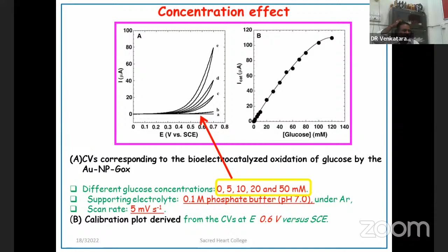The question is, even for a smaller change in your glucose level, like if I have 140 milligram per deciliter and some other person has 140.5 milligram, then that 0.5 milligram should be quantified exactly. For that purpose, people are trying to increase the sensitivity. How you can calculate the sensitivity is nothing but the slope of the linear portion of the curve. This we call the calibration curve, and the slope of this curve gives you the sensitivity. When you have a higher sensitivity, then a smaller change in glucose concentration can be indicated by your device.